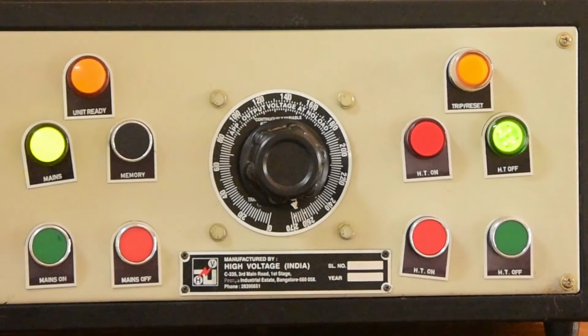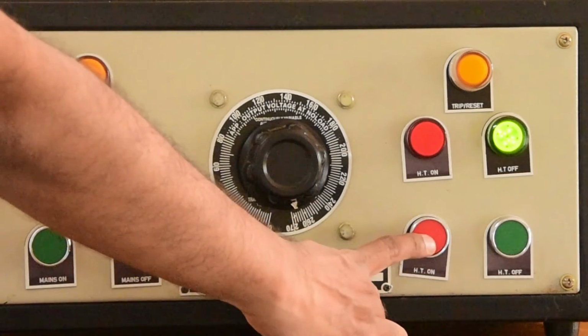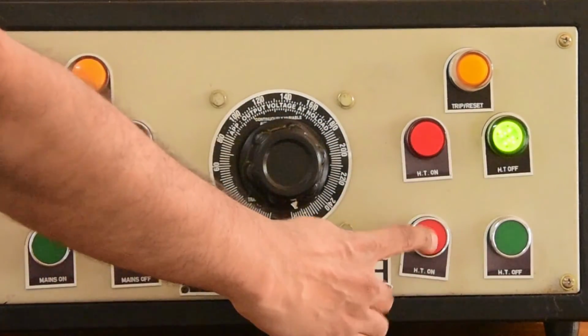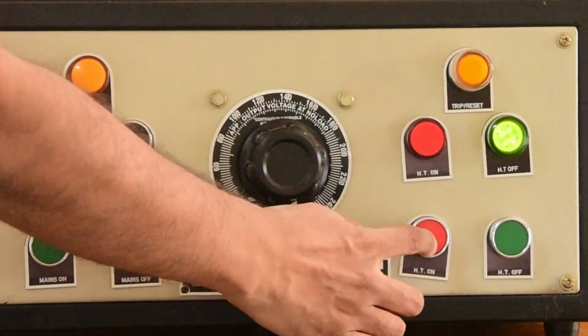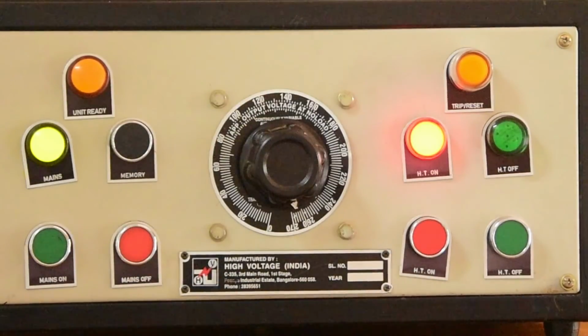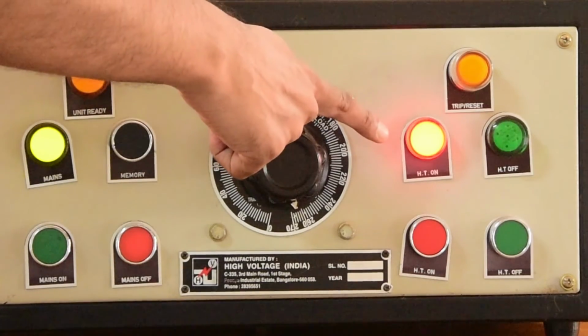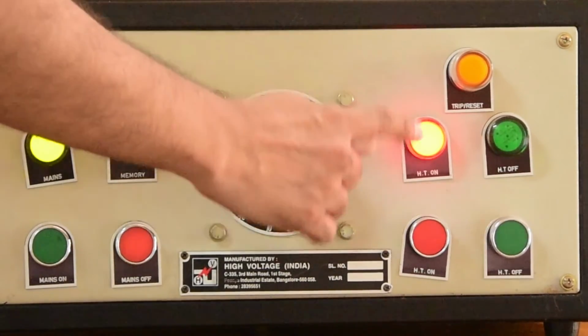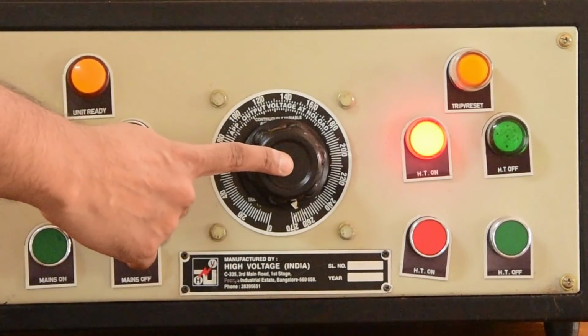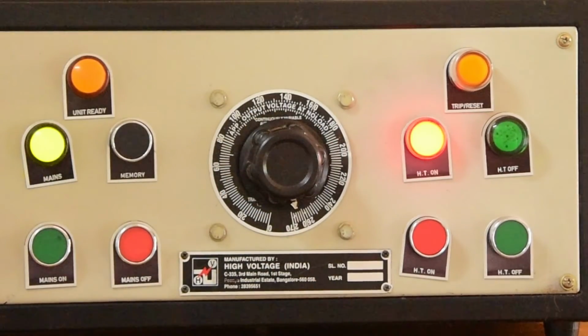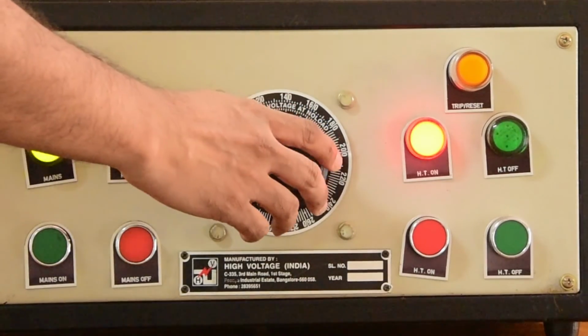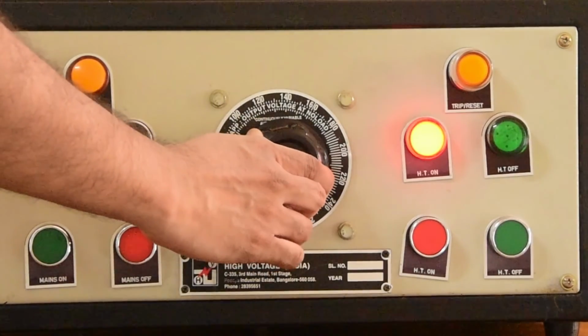Next, we are going to put HT on. Here it shows HT off. Now we are ready, this is the minimum position. So since this is ready, we can put HT on. As soon as we put HT on, you can observe the red lamp showing that now high voltage can be applied by controlling the panel. We have to be very careful while working with this assembly for the safety of the individual performing the experiment. So now I am going to apply the voltage.